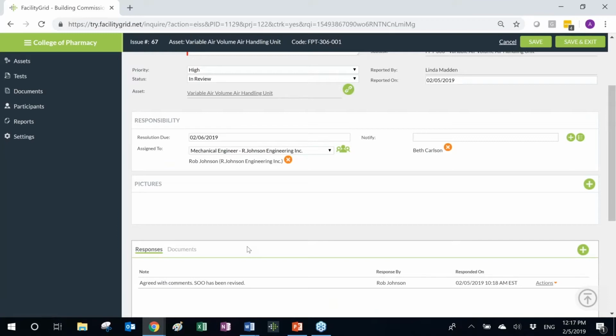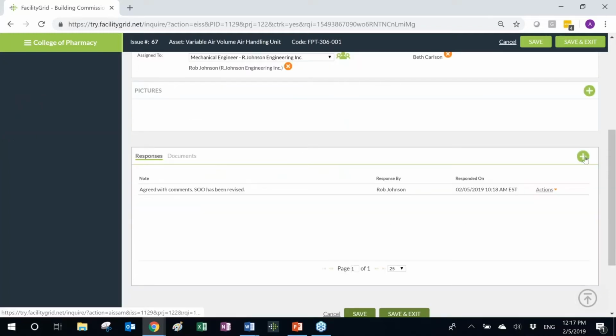Now it is the job of the commissioning agent to assign this issue to himself or herself and then revise the functional testing procedure, and then provide the response in the response section to indicate that the issue has been addressed, the sequence of operation has been revised, and the functional performance testing has been updated per the revised sequence of operation.